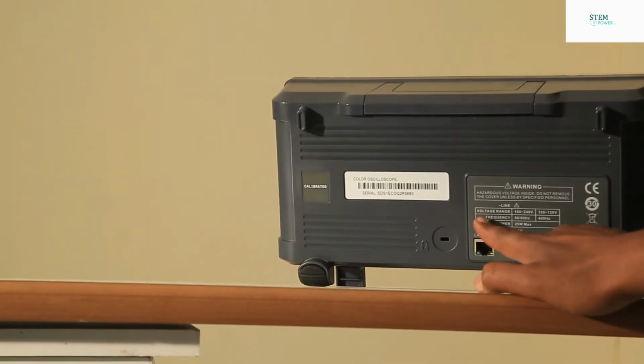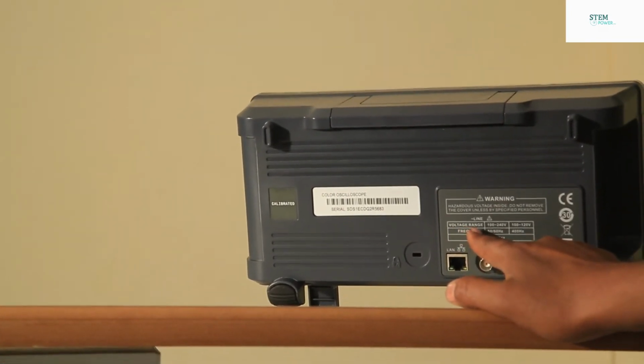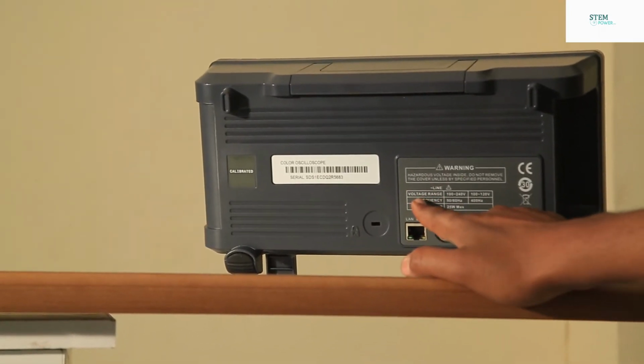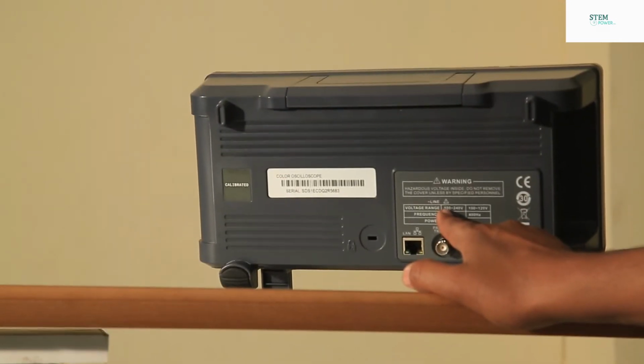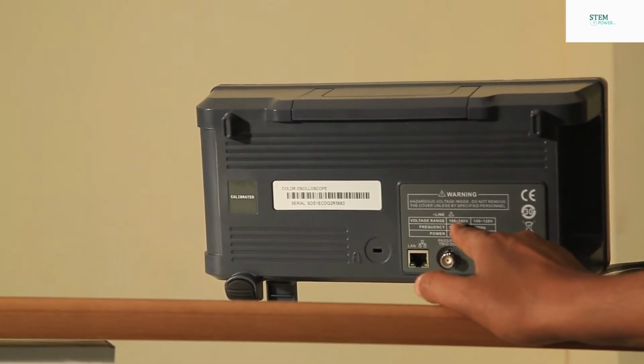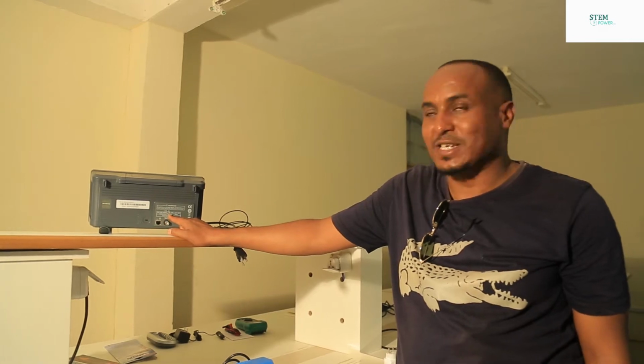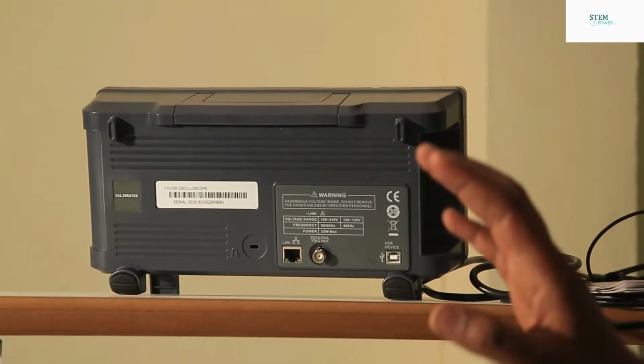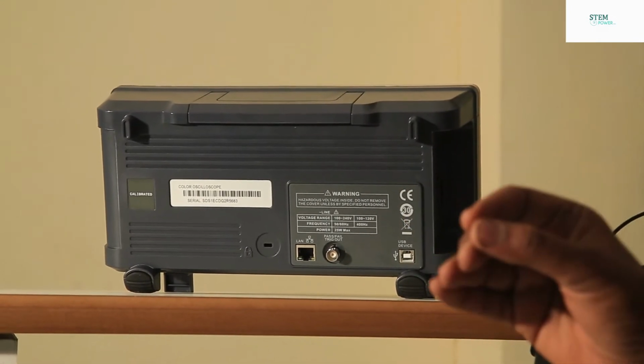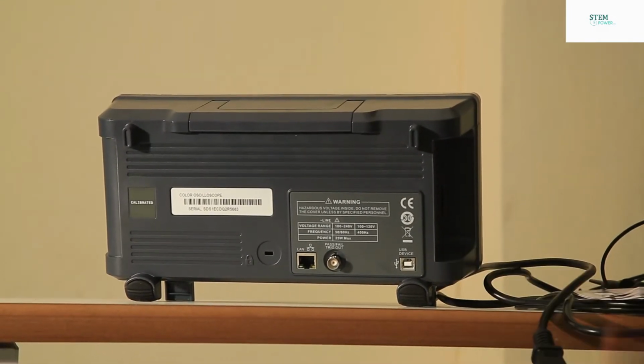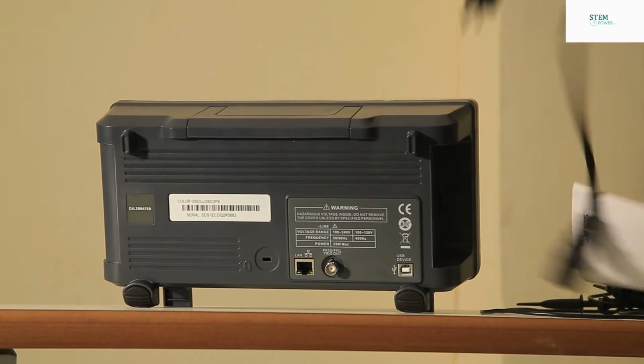First check the nameplate or rating of the instrument. The instrument says 100 to 240 volts at 50 or 60 hertz. Our power line is 50 hertz, 220 volts, so there is no difficulty.